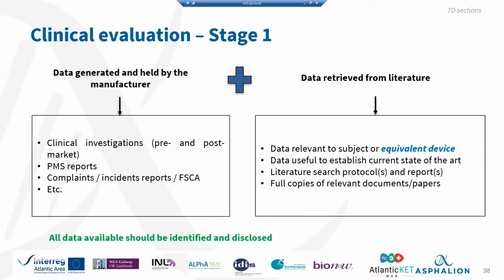It's important to mention that your notified body will ask for the papers, for the articles that you use in your clinical evaluation. That means you cannot base your information on the summary of the article. You need to retrieve this article because the notified body is going to ask for it. Okay, it's something obvious, but it should be stated.